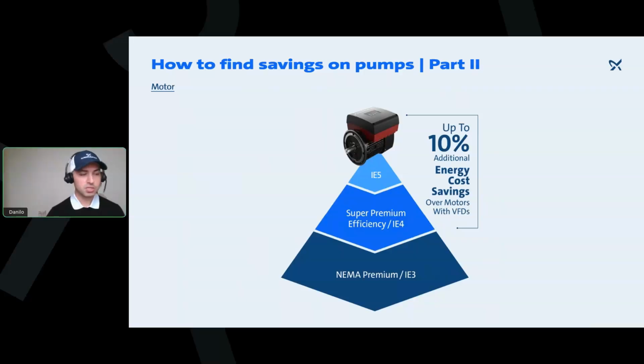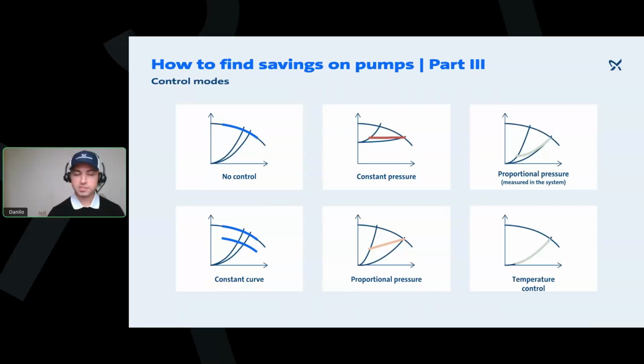So we've been on hydraulics and motors. The next thing to identify savings is how you control your pumps, right? Controlling the pumps is, again, very important because now you have to identify how far you are from the best efficiency point, right? If we're looking at more modern systems with drives and so on, you now have the capability to control the pump and run where you want to.